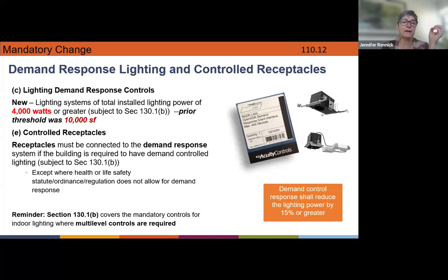One kind of tweak is if you're doing lighting demand response controls - instead of basing that on a 10,000 square foot threshold, which coincided with projects that also could need commissioning, the lighting system's total installed lighting power is now 4,000 watts. In my experience, 4,000 watts and 10,000 square feet are pretty close to each other, since a lot of our office buildings, designed by electrical engineers, ended up around a 0.4 watts per square foot LPD anyway.